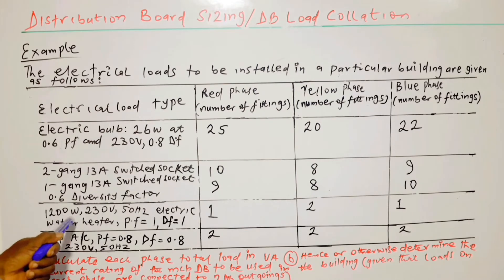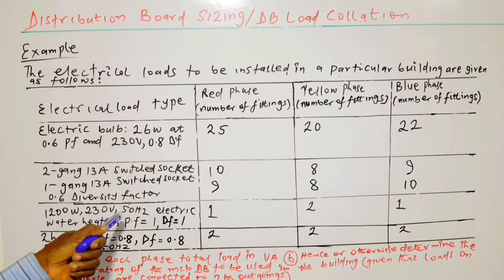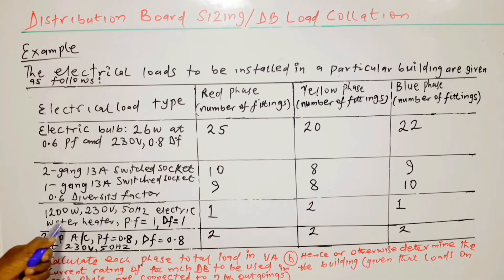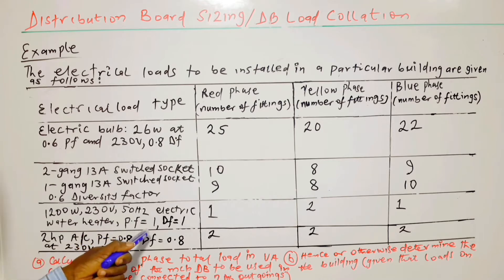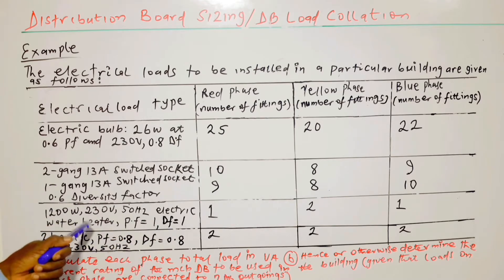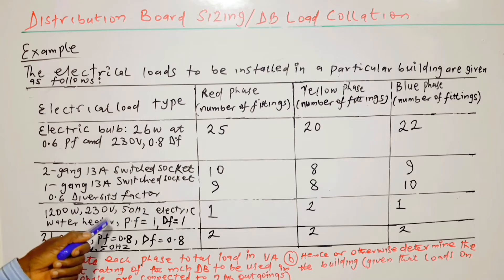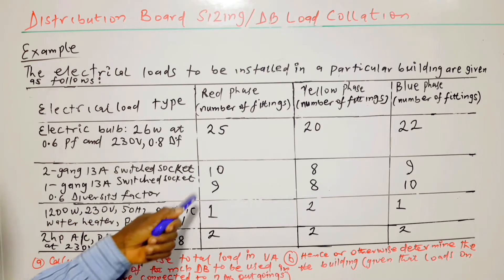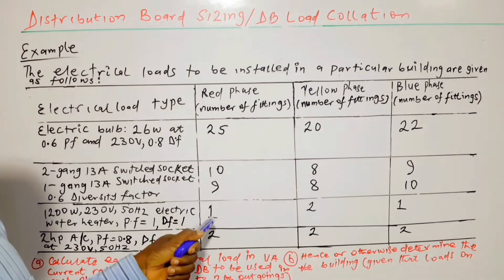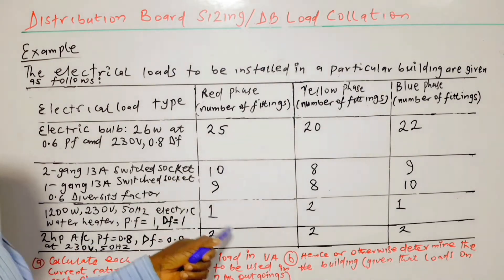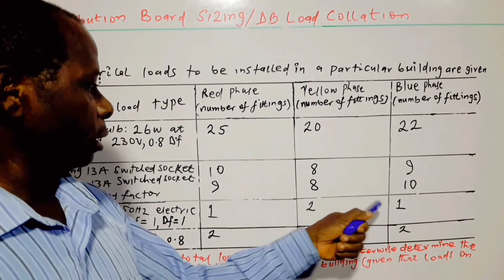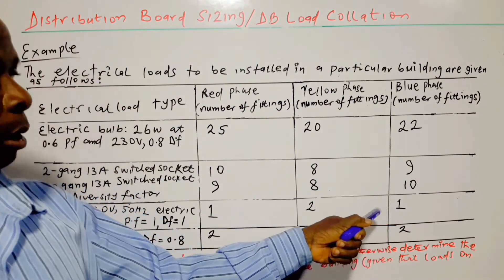Next is a 1,200-watt, 230-volt, 50-hertz electric water heater. The power factor is equal to 1 and the diversity factor is also equal to 1. It's a heating load — that's why the power factor is 1. Any heating load has a unity power factor. We have 1 water heater on the red phase, 2 on yellow phase, and 1 on blue phase.